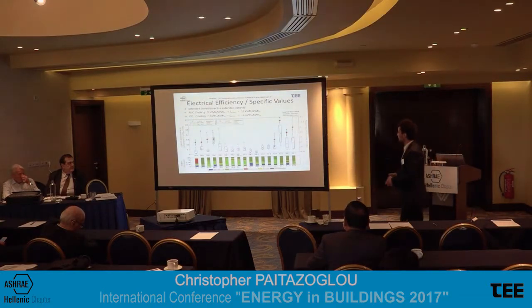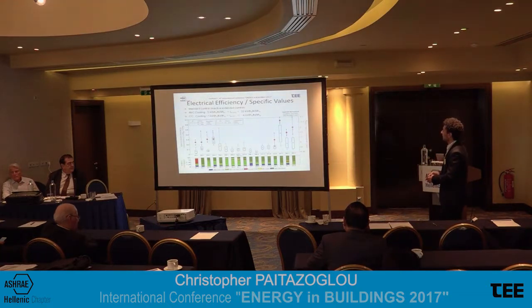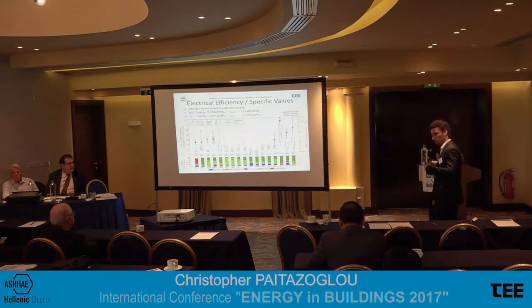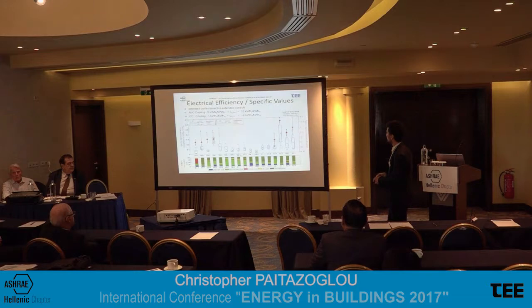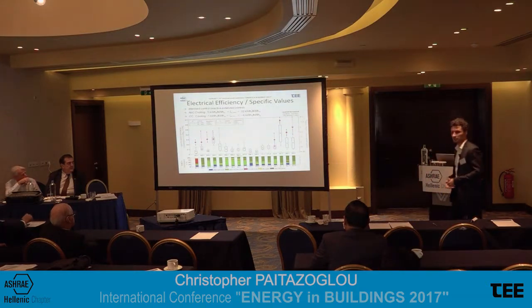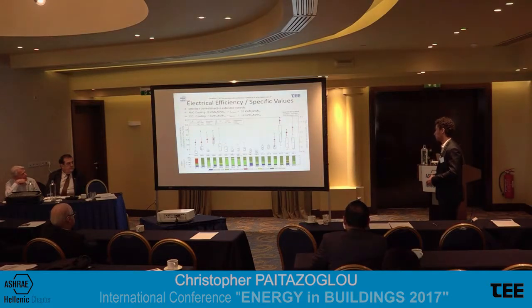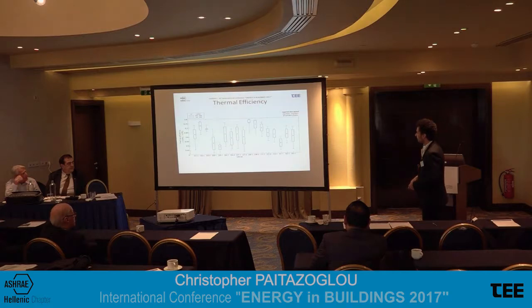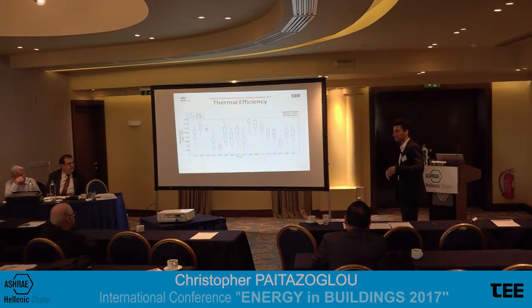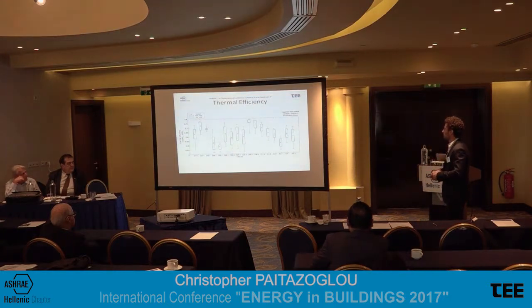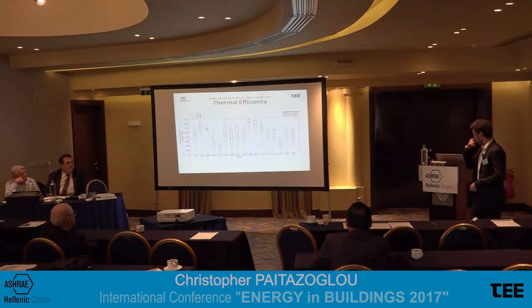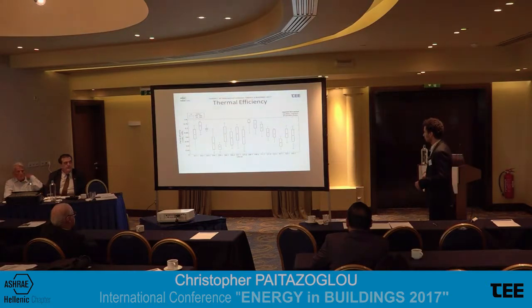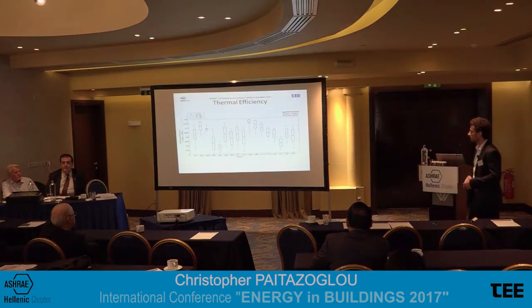If we compare that with the compression chiller, which is operating at a higher electrical consumption, or a lower COP, we see that even the most efficient model here provides an electrical COP of 4. That means that the absorption chiller can provide 6 or 7 times more than the compression chiller system in this field case. The thermal efficiency of the absorption chillers varies throughout the field test. Some are quite outstanding, reaching values of over 0.7, and some have lower values due to being operated at strong power load and having internal optimization problems that we're dealing with.